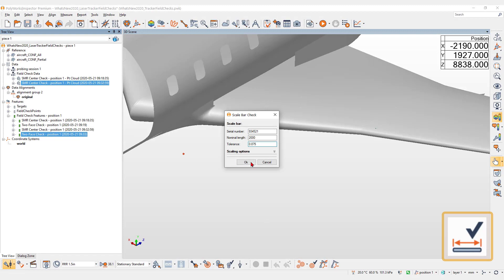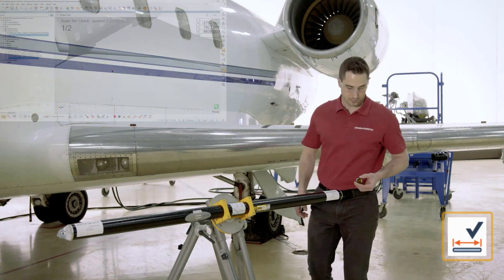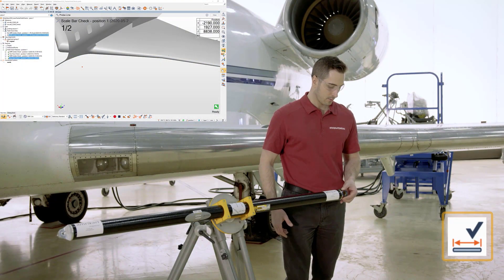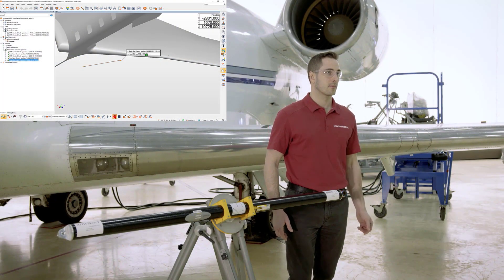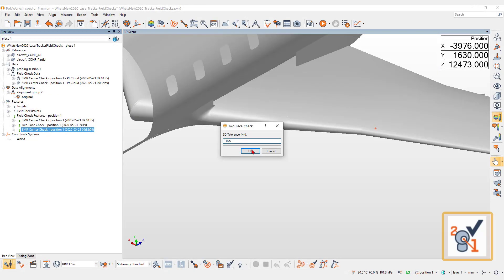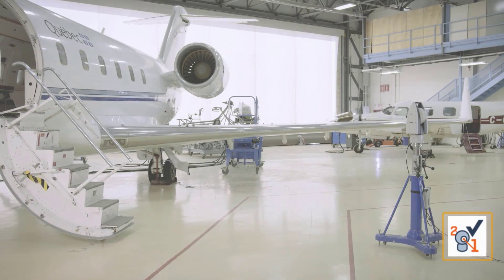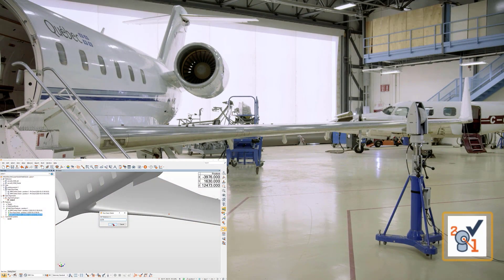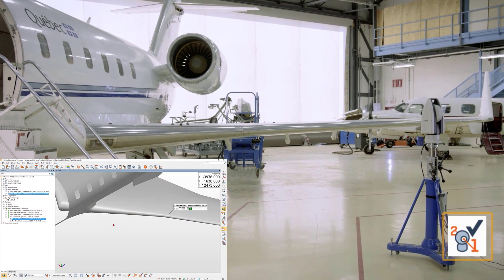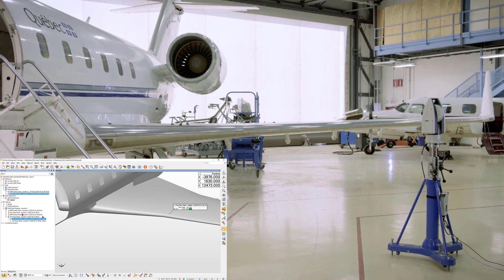Scale bar check to verify the accuracy of your distance measurement. And two-face check to ensure that front-face and back-face measurements are within tracker specifications.